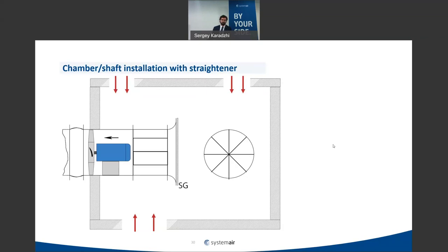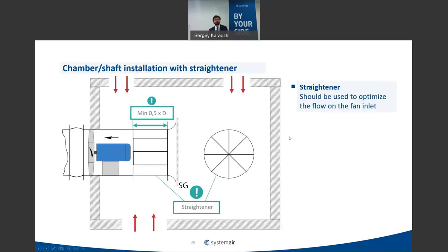If you have a chamber with air coming from different directions, it's always better to use a flow straightener, because non-uniform velocity profiles at the fan inlet influence its performance. In test rigs, a straightener is always placed after the damper to prevent any flow twist in front of the fan.